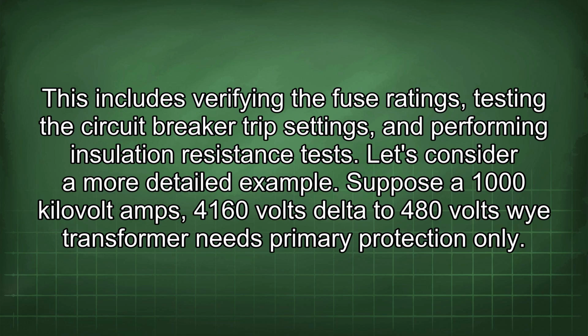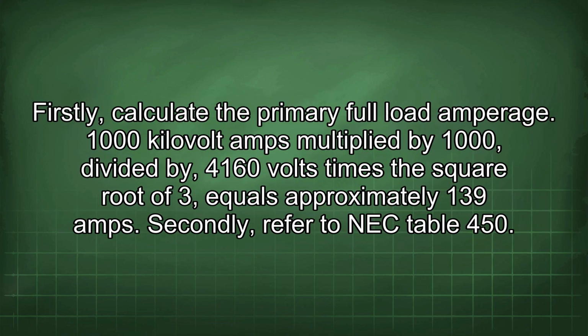Let's consider a more detailed example. Suppose a 1000 kVA, 4160 volts delta to 480 volts Y transformer needs primary protection only. Firstly, calculate the primary full load amperage. 1000 kVA multiplied by 1000, divided by 4160 volts times the square root of 3, equals approximately 139 amps.